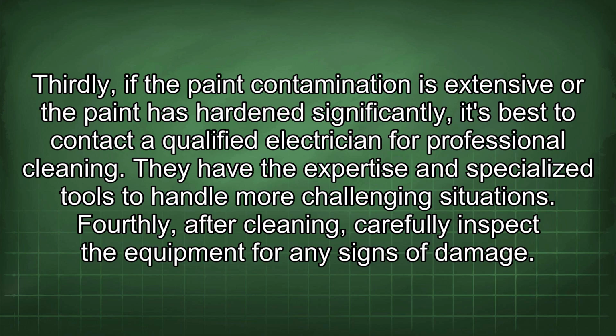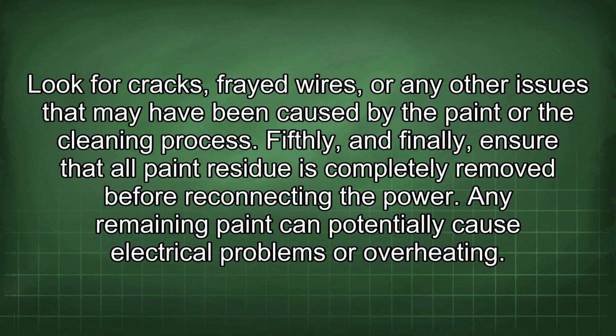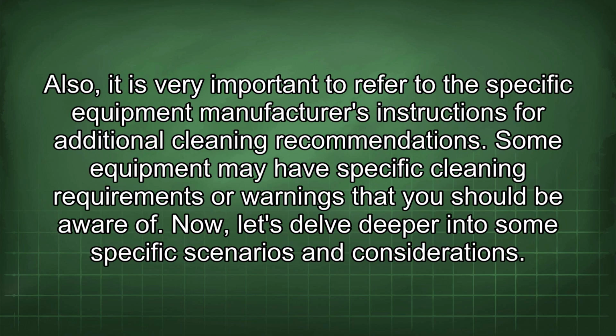Fourthly, after cleaning, carefully inspect the equipment for any signs of damage. Look for cracks, frayed wires, or any other issues that may have been caused by the paint or the cleaning process. Fifthly, and finally, ensure that all paint residue is completely removed before reconnecting the power. Any remaining paint can potentially cause electrical problems or overheating. Also, it is very important to refer to the specific equipment manufacturer's instructions for additional cleaning recommendations. Some equipment may have specific cleaning requirements or warnings that you should be aware of.